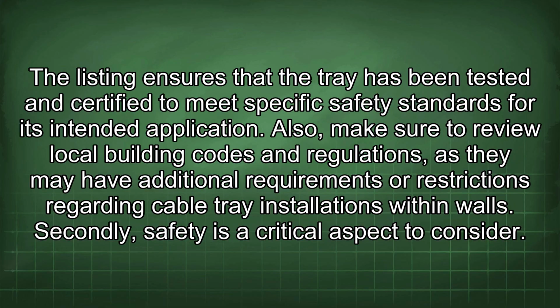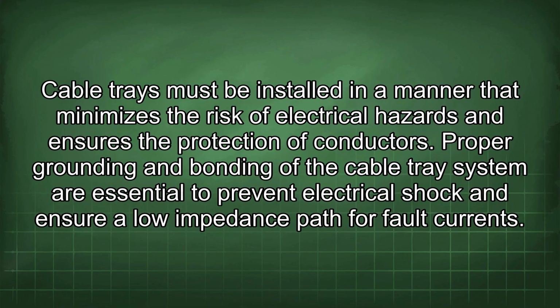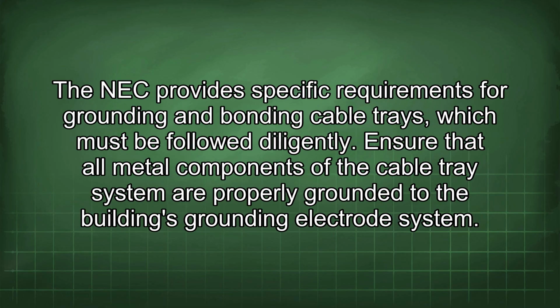tray installations within walls. Secondly, safety is a critical aspect to consider. Cable trays must be installed in a manner that minimizes the risk of electrical hazards and ensures the protection of conductors. Proper grounding and bonding of the cable tray system are essential to prevent electrical shock and ensure a low impedance path for fault currents. The NEC provides specific requirements for grounding and bonding cable trays, which must be followed diligently. Ensure that all metal components of the cable tray system are properly grounded to the building's grounding electrode system.